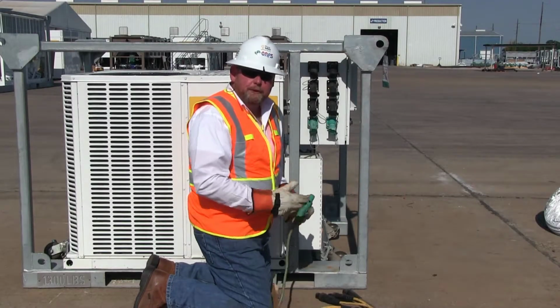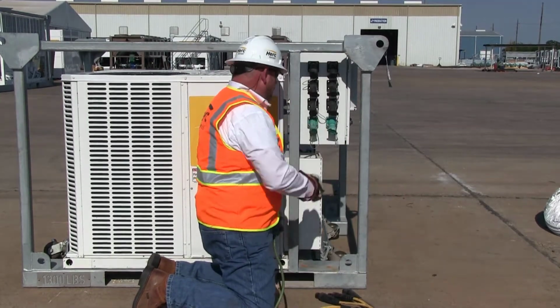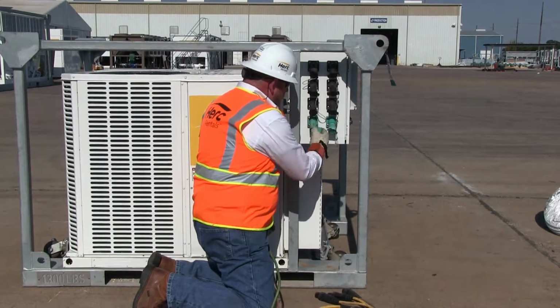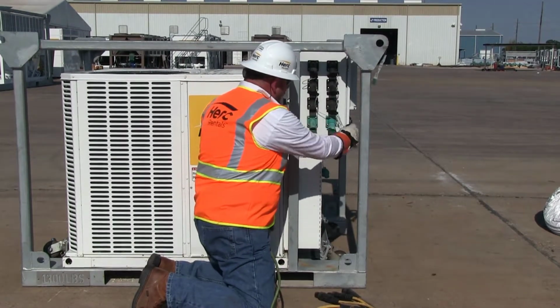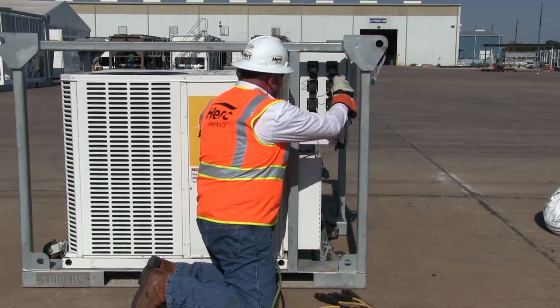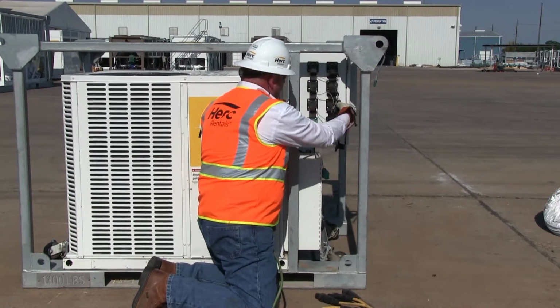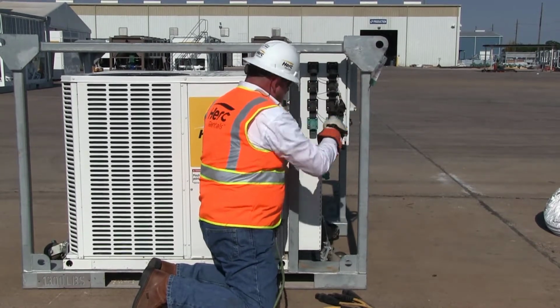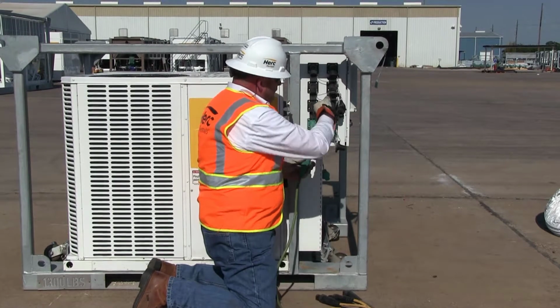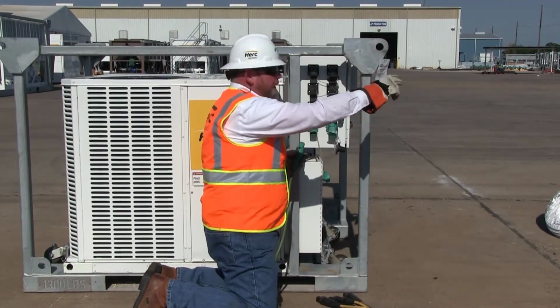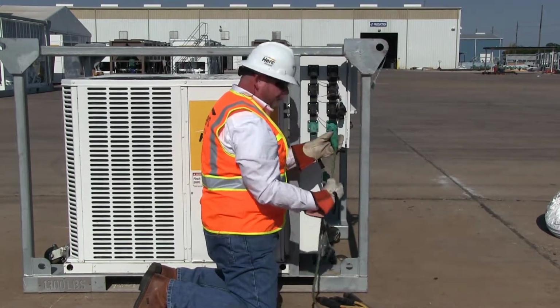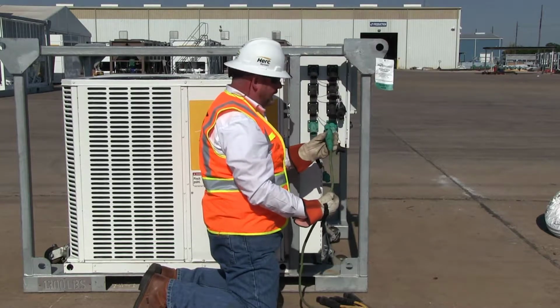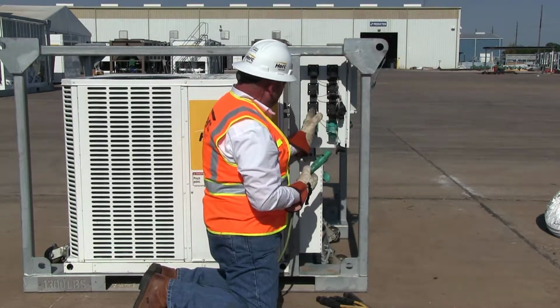All of our package units feature pass-through cam locks, and what that allows us to do, we're going to remove the dust and weather covers here on the metal cam locks. That allows us to bring in a primary feed and daisy chain another unit, 2 or 3 units together, whatever the cable capacity of the first unit is. So we've got parallel cam locks here.